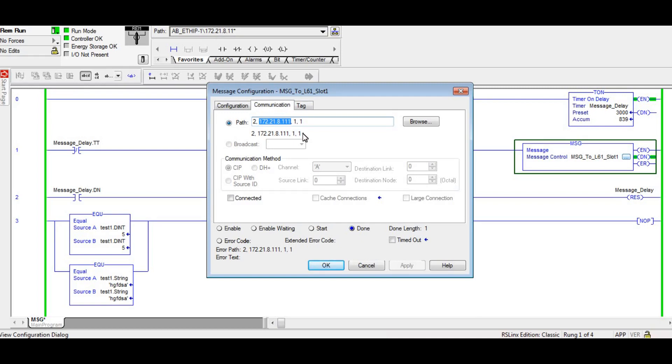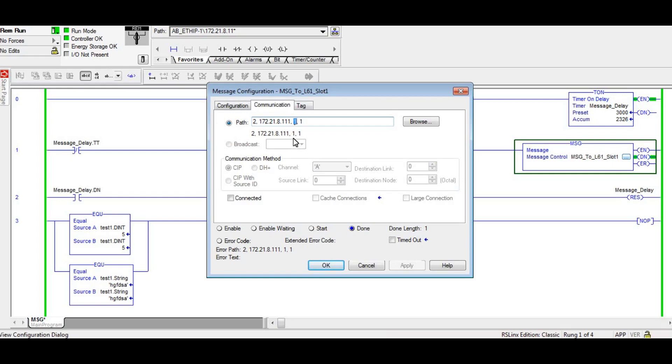In this case, because it is a Control Logix, an L61 that does not have onboard Ethernet, I'm actually at the IP address of the ENBT card that's in the Control Logix rack. So that's the IP address of the Ethernet card. In that case, I need to tell that Ethernet card look at your local backplane, which is the one, and then slot one.